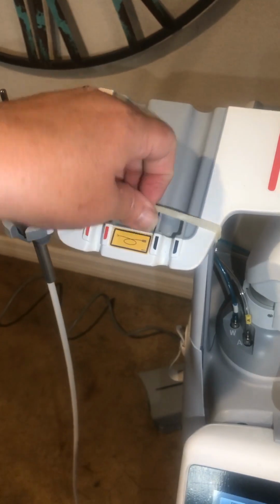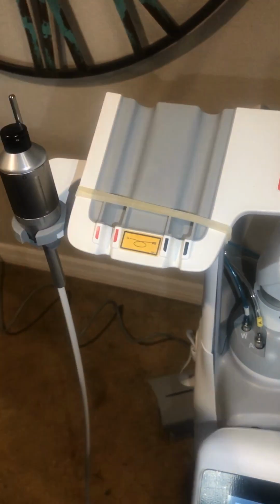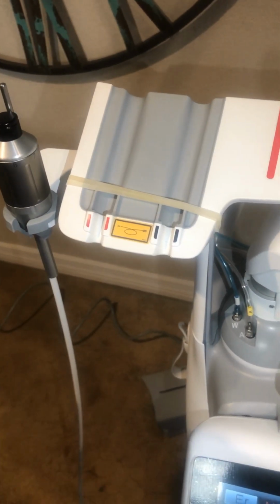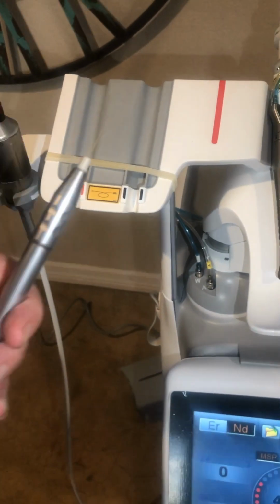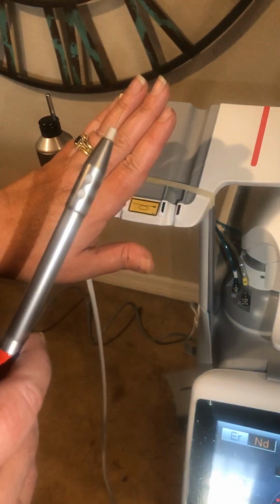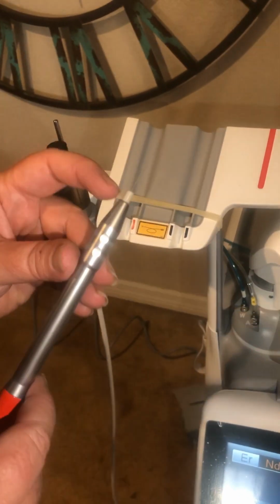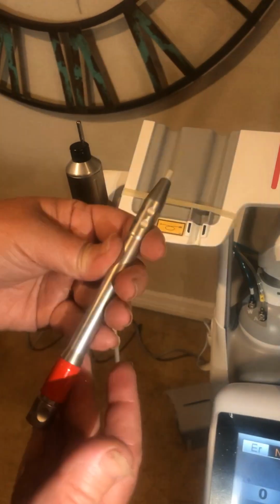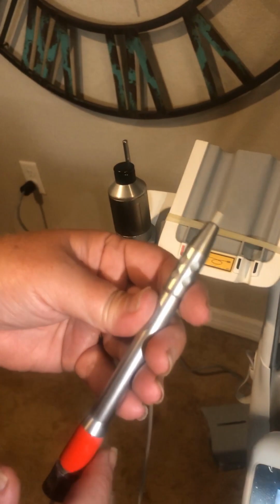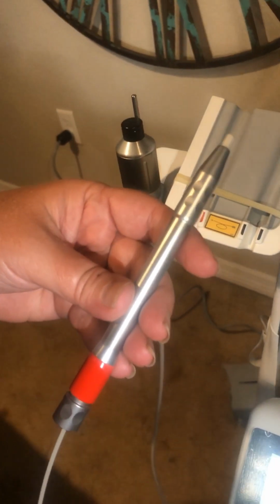So that'll help you. They do make a piece that actually can go here that's called an ND-YAG tray cover, and it will snap into place here, and it just lifts up and allows you to slide the handpiece out. I don't have that here with me right now, so to protect the handpiece, I just have some clear rubber bands, but it's definitely worth the added price to have that little cover, because if this drops and breaks this little rubber tip off, then the handpiece becomes inoperable. That's the only thing that would damage this handpiece and make it not work.